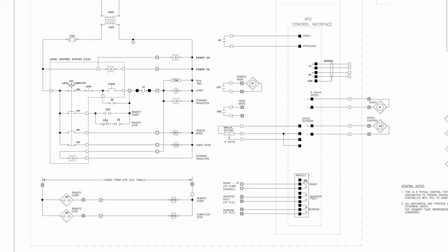Ready FF, it looks like there's a ready command. So this is coming from the drive. FF looks like it's a signal from the drive. So if the drive's not ready to run, the drive won't run. Once whatever fault that is clears, or whatever state that is allows it to run, then it will run in local or remote. This is the running indication back to the PLC, and this is the fault indication back to the PLC.